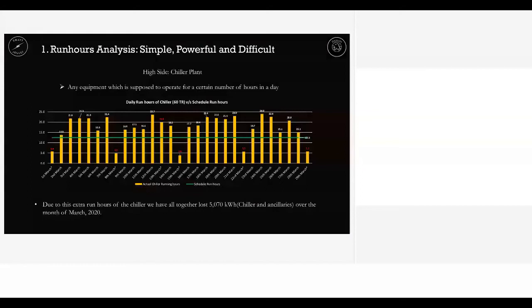This is another example, in the case of the chiller. As I've told, the AHU is supposed to shut down at a certain time, and the chiller is also supposed to shut down at a certain time. If we have data, we know that this equipment is supposed to run say 12 hours in a day, 12.5 hours, the green line in between. This shows that this equipment should only be running for 12.5 hours in a day. But on many days it is running for more.